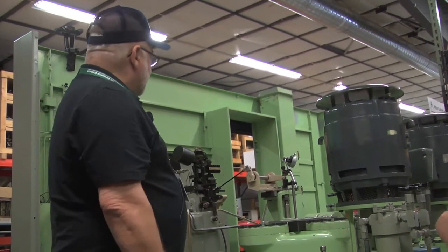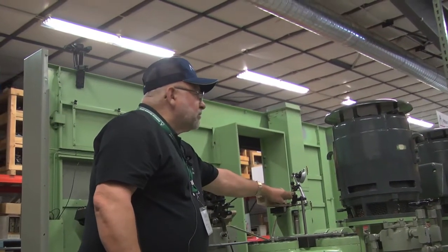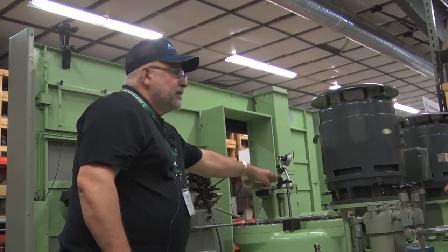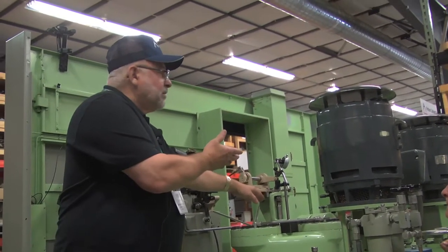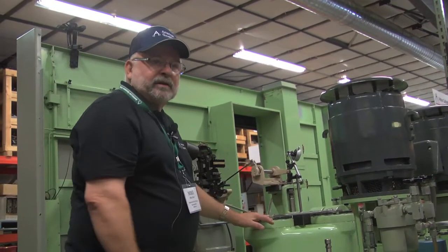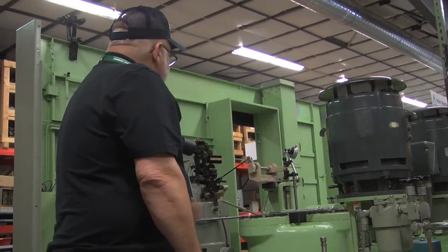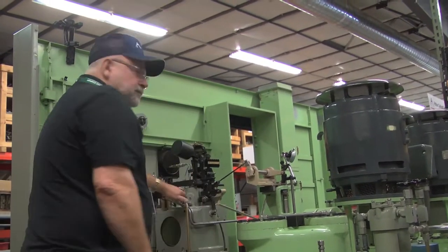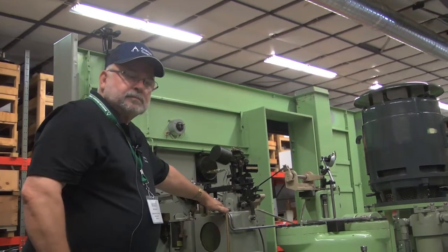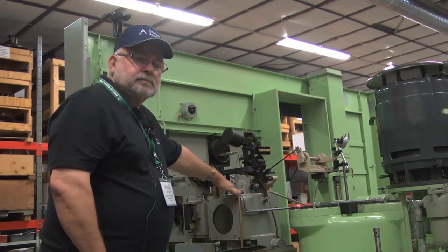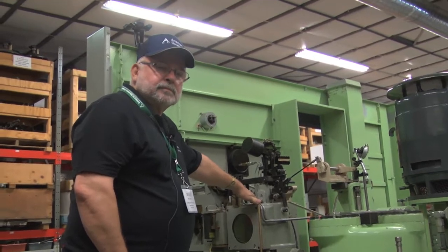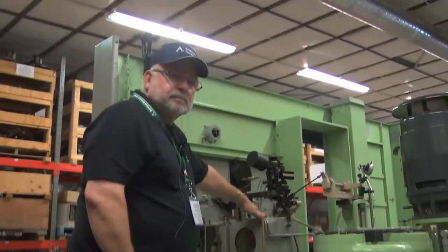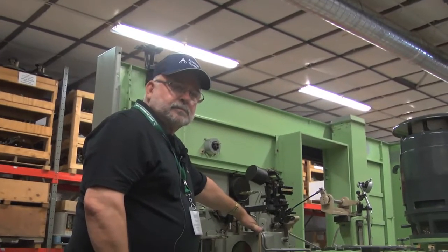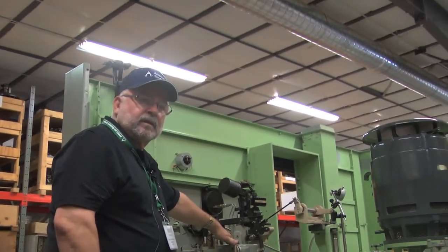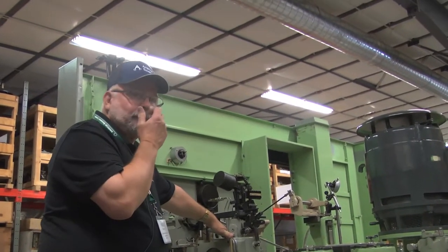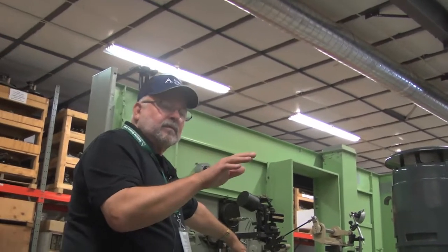Right. But when I walked out to the unit, this was going about 45 thousandths, which is going to make your pumps run more and cost you more money. Before we did calibration on all 8 of our units, you walked from one unit to another, and those nuts wouldn't be equal on each side. Actually, on unit 3, the nuts were almost touching the casting on the close.